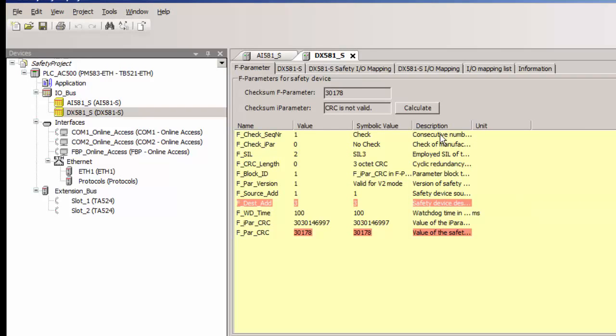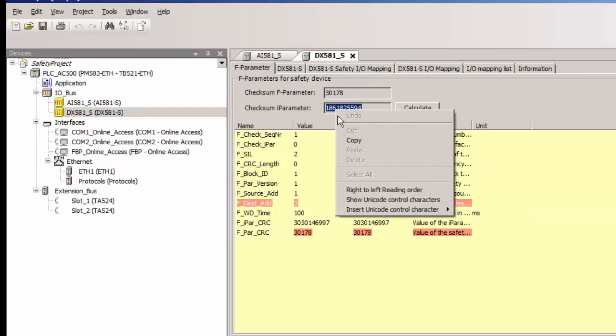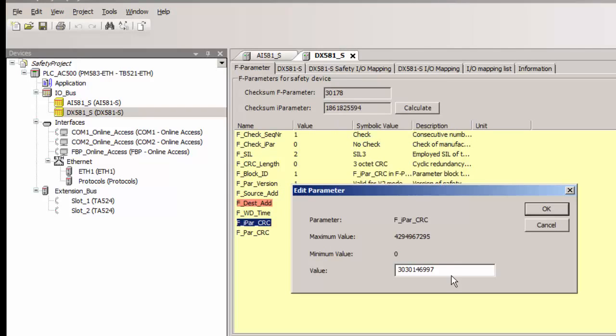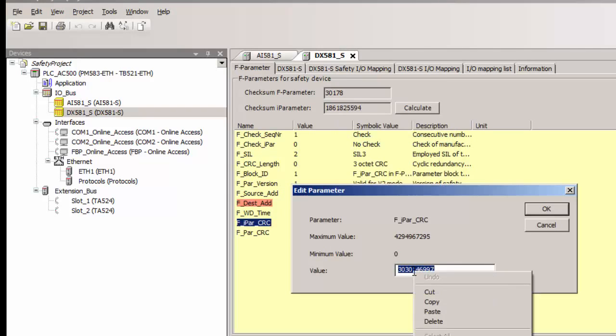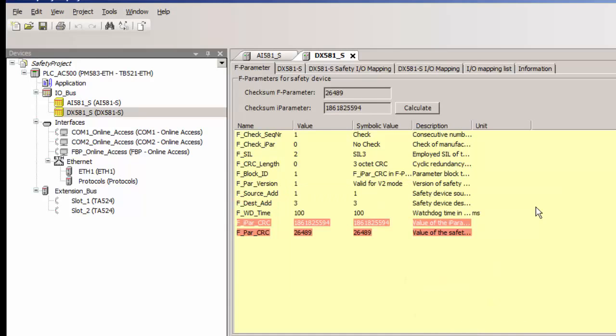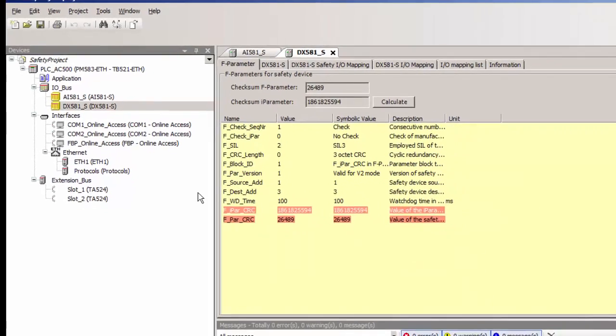Note this: when we change the default failsafe parameter setting one has to manually update the IPAR CRC parameter as shown on the screen. This manual setting is needed as per the safety standards programming requirements.